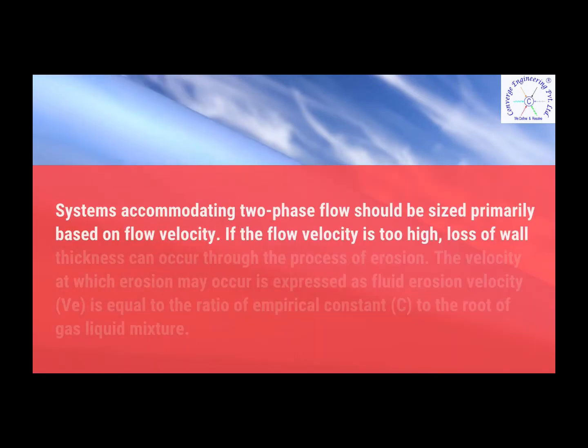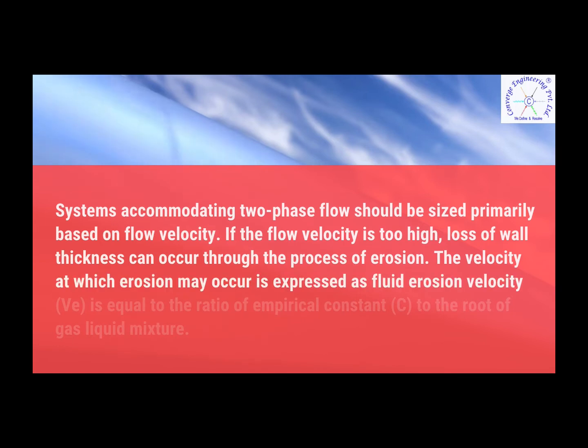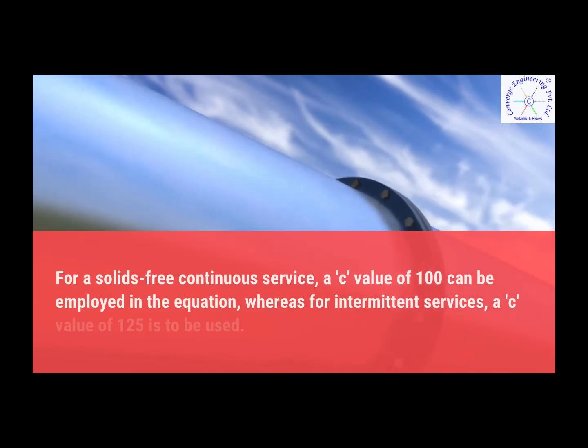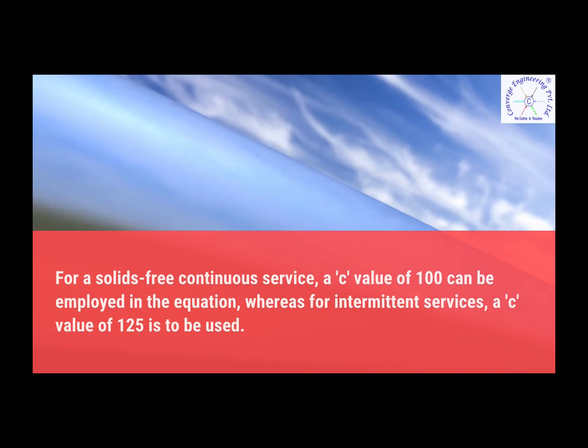What is meant by erosion velocity? Systems accommodating two-phase flow should be sized primarily based on flow velocity. If the flow velocity is too high, loss of wall thickness can occur through the process of erosion. The velocity at which erosion may occur is expressed as fluid erosion velocity, equal to the ratio of an empirical constant to the root of gas-liquid mixture density. For solids-free continuous service, a 'c' value of 100 can be employed in the equation, whereas for intermittent services, a 'c' value of 125 is to be used.